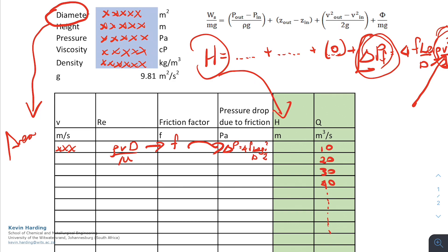Please don't forget, if there are bends and valves and fittings, you would calculate this delta PF in exactly the same way to take into account all of those. You might want to put those either in a column of their own, so add another column in, or you might want to put that into this area of constants, as I've got in the top.